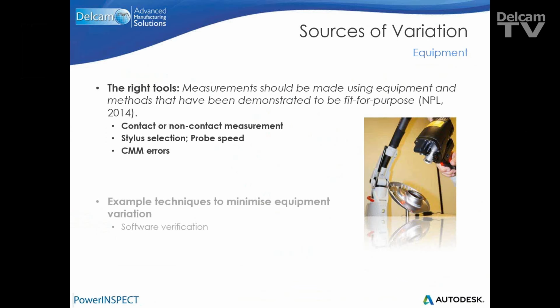And then we'll talk about interface, which is software and controller. So is there any sort of manipulation of data? Some of the more modern equipment now is using mass data collection, which means you have filters, averaging going on throughout the system. So there is some form of interface. Even on a dial test indicator, there is an interface, and that interface is you. You're reading the needle on a dial and making an interpretation of whether it's touching the left hand or the right hand indication. So interface is the third, and then the fourth one is the scales, the resolution of the scales. How are the scales performing?